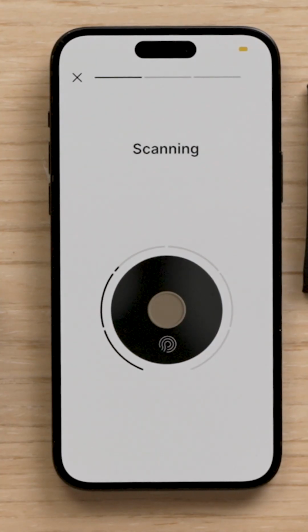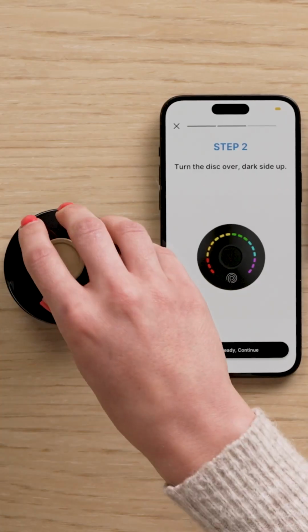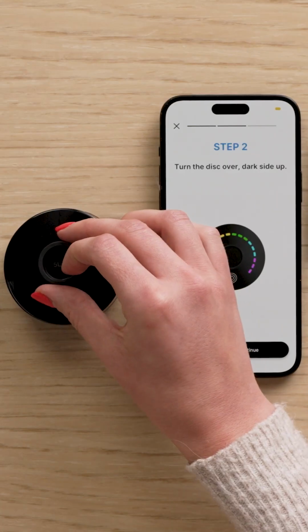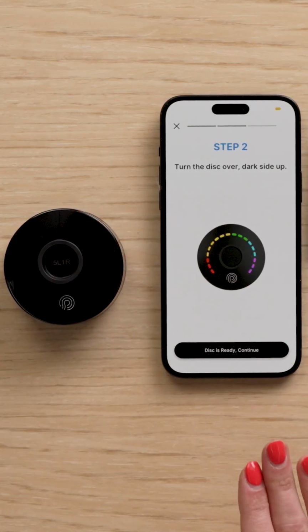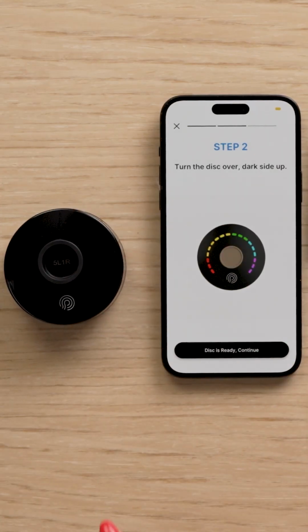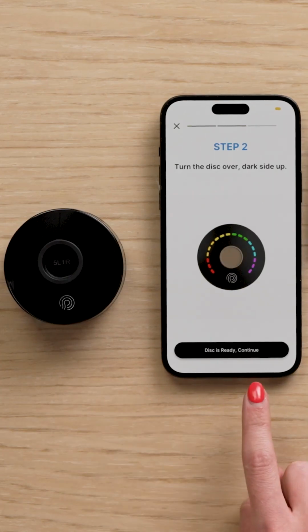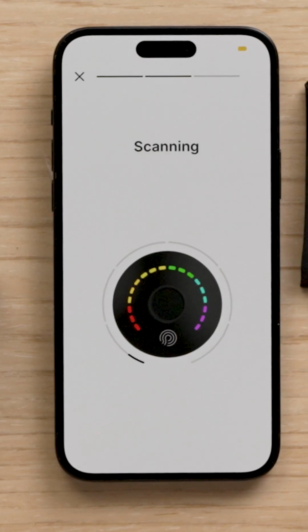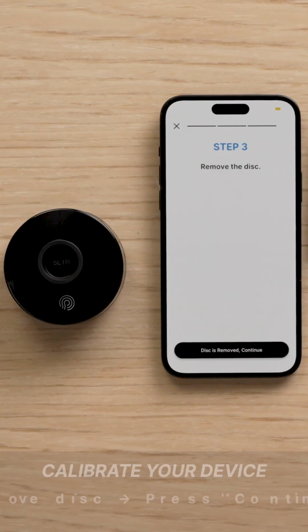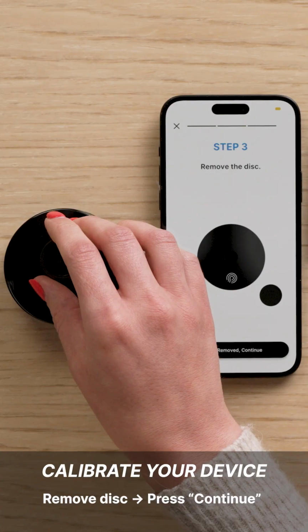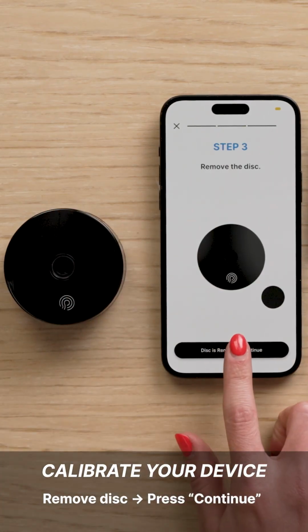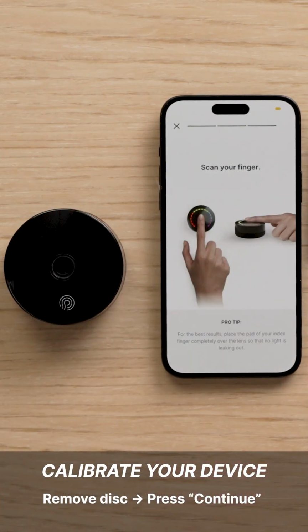And what we're doing here is setting unique values for the device as part of its calibration process. Once that step is complete, you'll be prompted to turn over the calibration disc so that the colored side is now facing the lens. Once that has been placed, press Disc is ready, continue. This process is now setting the unique calibration algorithm into the device as part of the calibration process. Now lastly, remove the disc, press Disc is ready, continue. Then you will scan your finger.